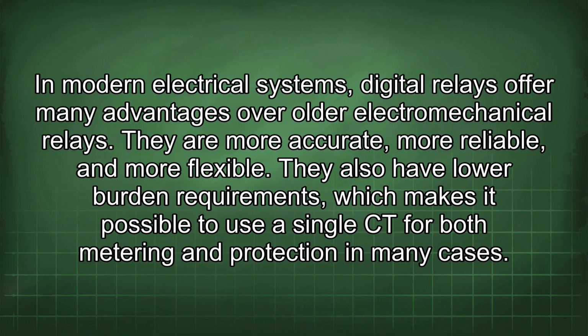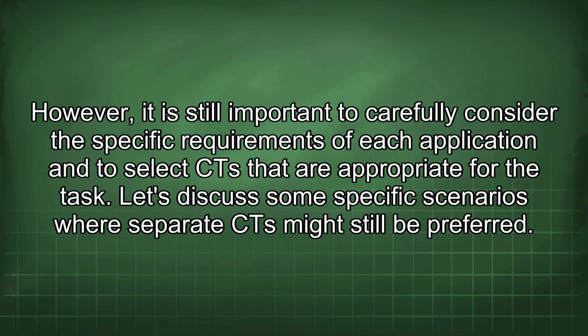In modern electrical systems, digital relays offer many advantages over older electromechanical relays. They are more accurate, more reliable, and more flexible. They also have lower burden requirements, which makes it possible to use a single CT for both metering and protection in many cases. However, it is still important to carefully consider the specific requirements of each application and to select CT that are appropriate for the task. Let's discuss some specific scenarios where separate CT might still be preferred.